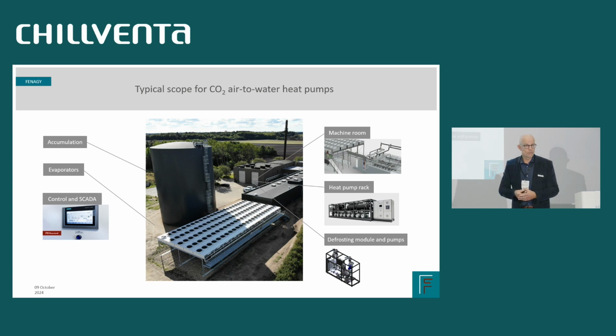So a project could look like this. It's probably a pretty average project. In this case, it's a 4 megawatt heat pump. It's CO2 as refrigerant. And here you see the outdoor energy collectors. So those are the heat exchangers taking the heat from ambient air. A lot of the heat is actually condensation of the humid air. So there's a lot of water dripping from the collectors because we're cooling air below the dew point.